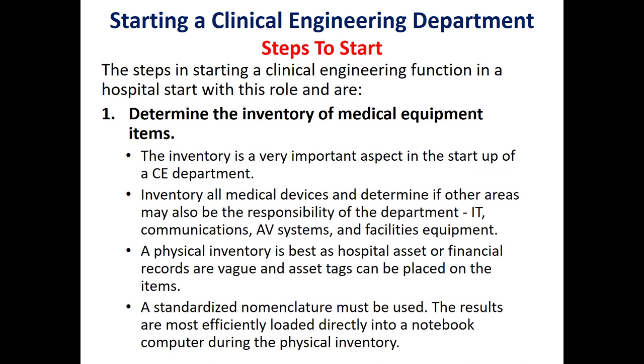We will start with the first step, which is to determine the inventory of medical equipment items. It is a very important aspect in the start-up of the clinical engineering department. We should inventory all medical devices and determine if other areas may also be the responsibility of the department, such as IT, communications, AV systems, and facilities equipment.